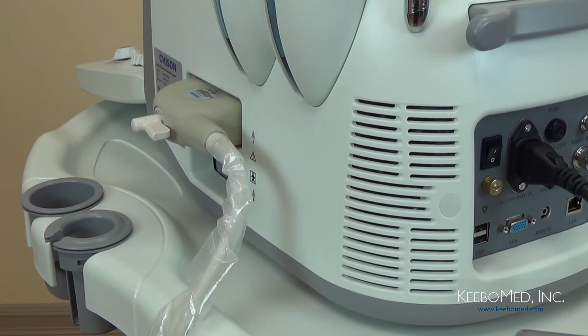Let's now review the proper way to remove the probe from the system. First, turn off the unit and put the probe head inside of the probe holder. Second, turn the lock knob in the counterclockwise direction to the open position and then remove the probe carefully from the probe socket.